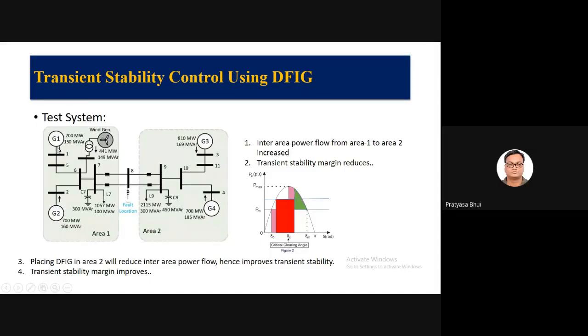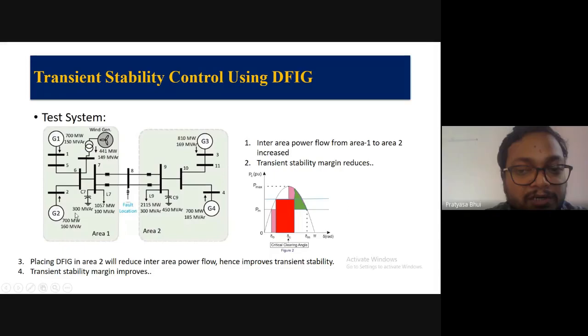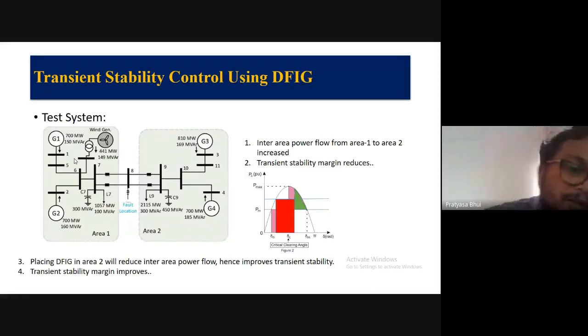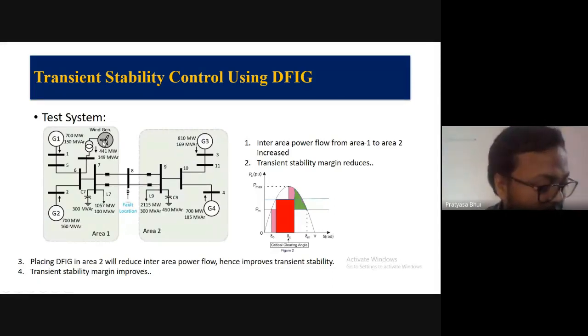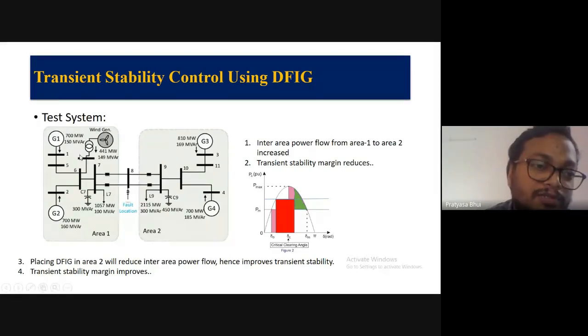So that you convert it. Generators 1 and 2, because the loads are the same and the angle differences between the generators are the same, so it will draw more power from generators 1 and 2. Eventually it will try to decelerate generators 1 and 2. Now reducing generation from wind is like putting more load on generators 1 and 2, so it will try to decelerate the generators.